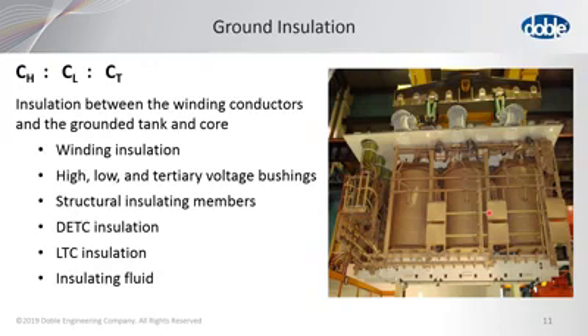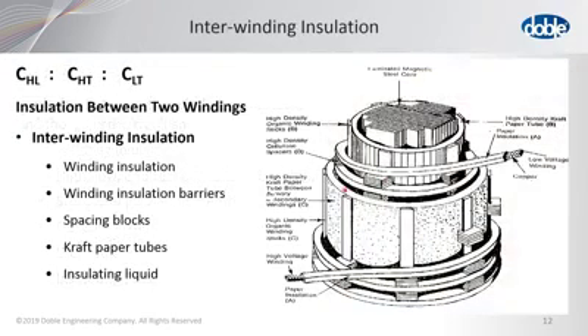ground insulation test. Now the inter-winding test is a little different in that you get the insulation that's between the high and low and tertiary windings. It could be the winding insulation. Now this is the insulation right here that we're talking about. The insulation barriers, like this is part of the barriers. The spacing blocks are these right here.